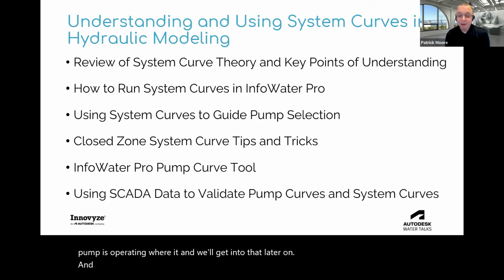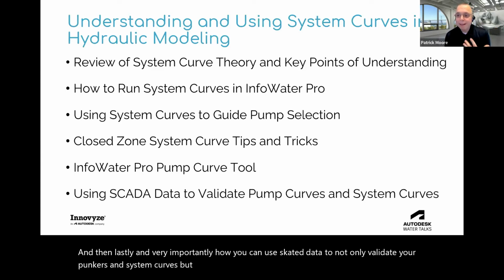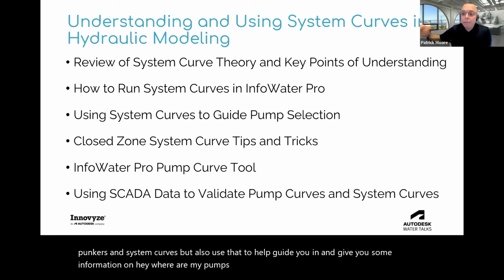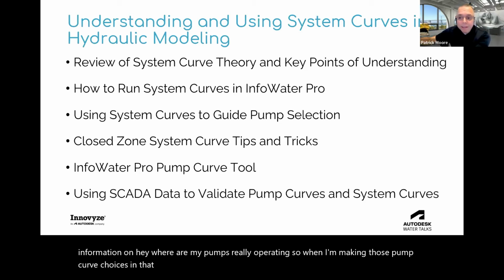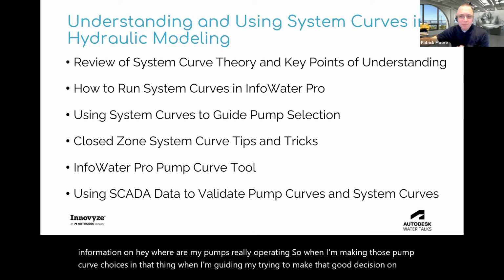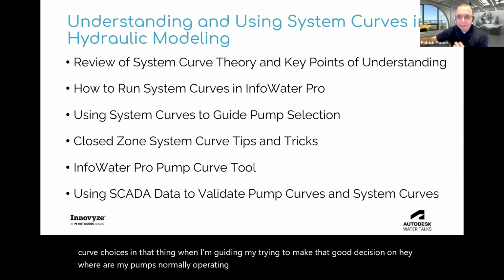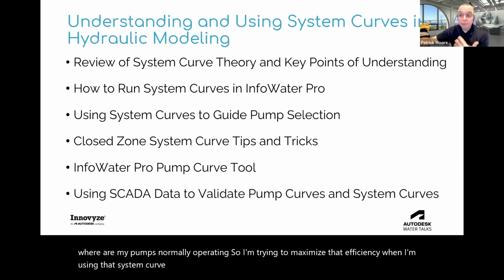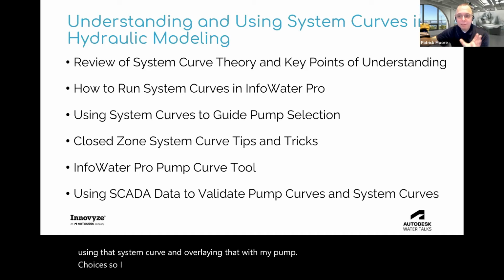And then lastly, and very importantly, how you can use SCADA data to not only validate your pump curves and system curves, but also use that to give you some information on where your pumps are really operating. So when I'm making those pump curve choices, when I'm trying to make that good decision on where my pumps are normally operating, I'm trying to maximize that efficiency when I'm using that system curve and overlaying that with my pump choices, so I can best choose where I really want to maximize that efficiency.